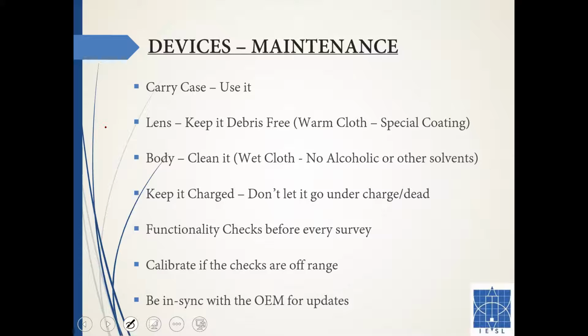Maintenance, all right. I have seen many poor maintenance practices. Your thermal imager usually comes with a carry case. If that's an industrial camera, there's a very high probability that it has a plastic case. Always use it as much as possible when you're going around the site. And lenses and external optics, keep them dust-free, debris-free. Please remember that your sensor covering, the lenses, have a special coating on them, right? This coating enables the infrared photons to get onto your thermal sensor. If you try to remove that coating, you are obviously wearing off your camera. Use only soft cloths. They can be wet, but no alcohol and other solvents, right? Solvents can affect the special non-reflective coating.